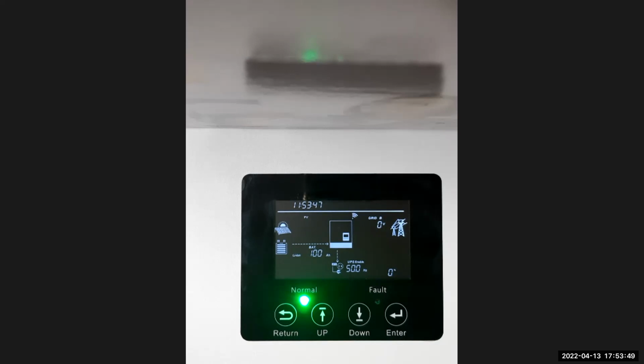So PVA is positive. You're going to take one wire from the PVA positive running to the PVB positive, and from the PVA negative running to the PVB negative. So you're basically going to bridge your 2 MPPTs in parallel mode and only have one input coming in. You can put that one input on PVA negative and positive, and as soon as you parallel the 2 MPPTs, the load will be shared between them. That means the amps will be more than enough. You'll have technically 26 amps to run off them. So then you can have a string that comes down of up to 26 amps if you do it this method.